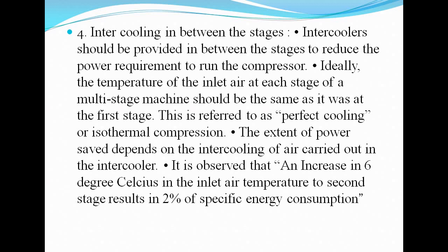It is observed that an increase of 6 degrees Celsius in the inlet air temperature to the second stage results in a 2% increase in specific energy consumption. So if there is an increase of 6 degrees centigrade in the inlet of the second stage, then there would be an increase in energy consumption by 2%.